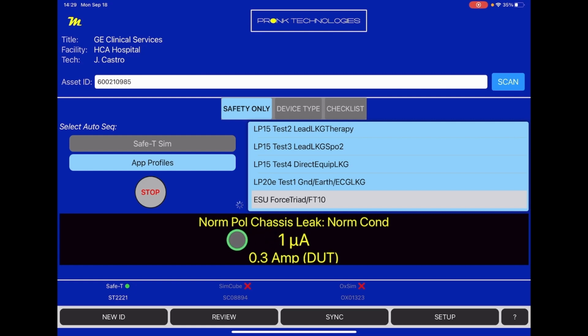Since we selected to do a longer boot up time to allow the unit to boot up, you'll see that each test will take a little longer to run, accommodating for the time for the device to actually turn on and boot up completely. So as the unit is turning on, you'll see it's performing each individual test, and again it's capturing each individual result, and it's collecting this information so that at the end of the testing we're going to have a complete electronic service report.